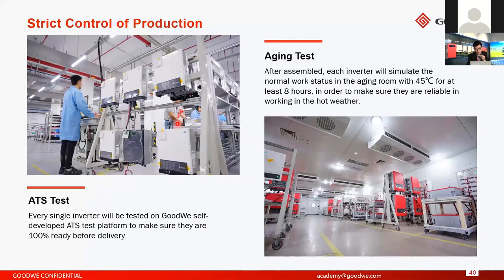Here are some tests in our production line. The ATS test is a 100% test, which means each inverter needs to do this test. The ATS test tests the communication and the control code, to make sure each inverter works normally before delivery to the customers. The next one is the aging test. Before packaging and delivery, the inverter is put into the aging room. The room temperature is 45 degrees, and the inverter works in this room for at least 8 hours to make sure everything is fine. Then we take the inverter out of this room, package it and deliver it to the customers.